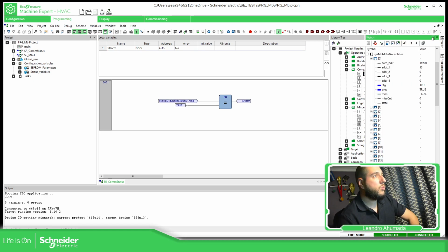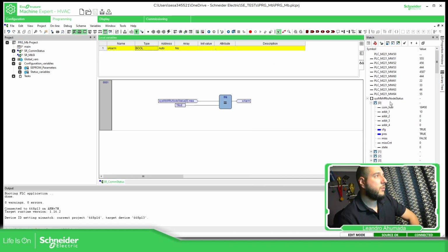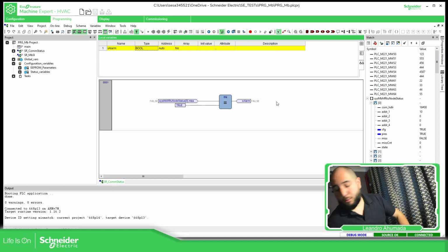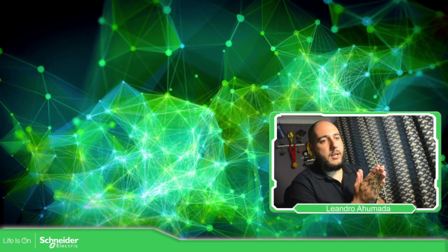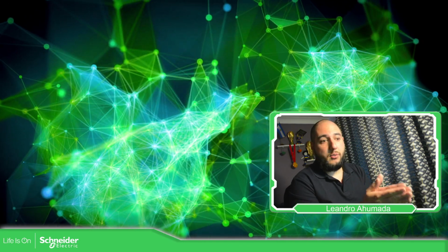So if we go to the watch, here you can see, now you should be able to see the status. Now if I remove the cable, the alarm is true, and you get the alarm, and then you can do whatever you want. Now I'm going to put it back. And that's it. There is no more alarm. So I think I didn't forget anything. This is how you can troubleshoot the IOScanner in case there is an issue.